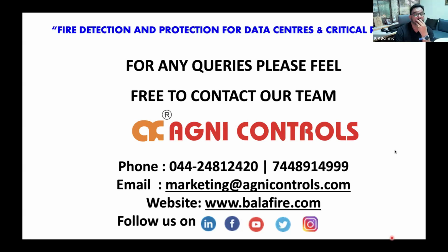Wow, nice. Biju is asking, what is the possibility of an open source protocol? This is not the tech. I think most of the panels are now open protocol. I don't know if the closed protocol ones are still there, but this cannot be answered by us here. What is your thought on that? It is a major issue, because when you have a closed protocol, you're at the mercy of the manufacturer. Even if tomorrow they increase the detector price by 10 times, you need to buy, because no other detector will work with the panel. You have to go with the vendor. There are a lot of open protocol panels that also come in the market. You can be wise in selecting which make, whether you want closed protocol or open protocol.